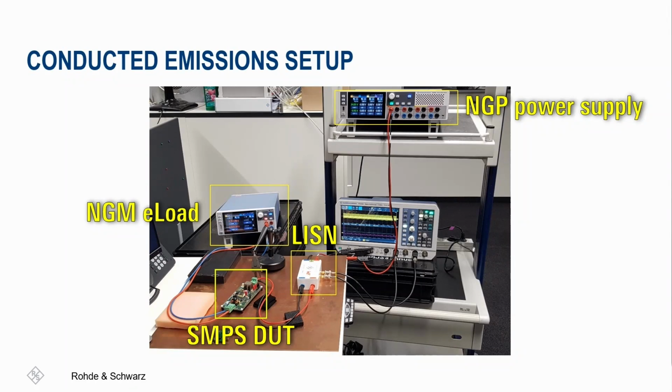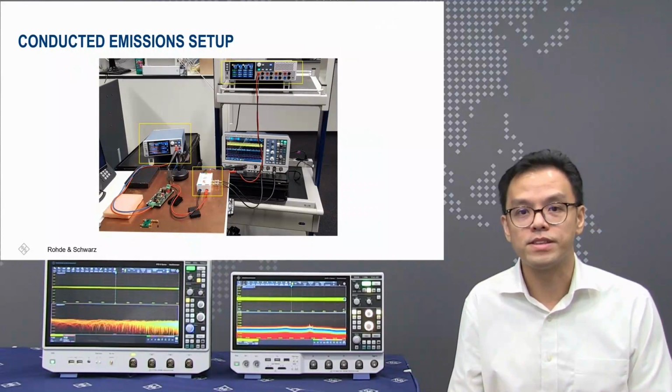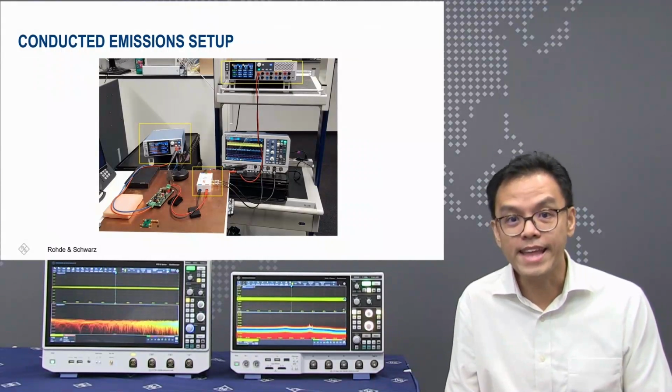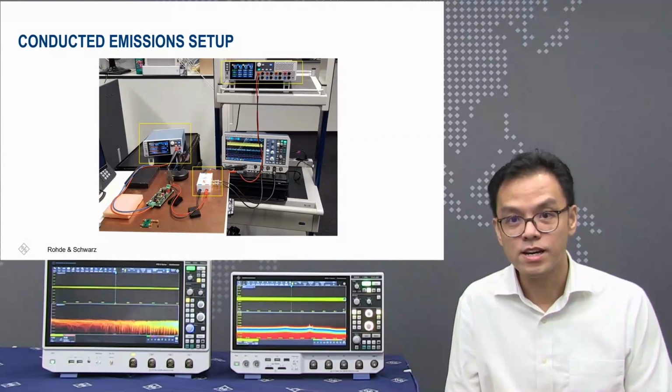From the LISN, you can observe we also connected the coaxial cable feeding into the RTM3000 oscilloscope. Alternatively, you can also replace the scope with the powerful RTO6, offering superior signal fidelity and exceptional processing capabilities to handle the Vp and Vn for noise calculation and characterization.